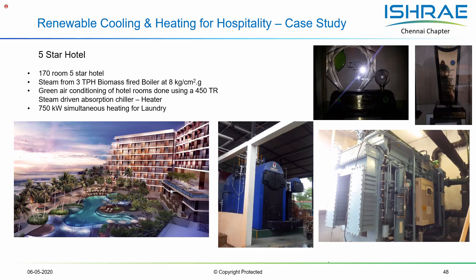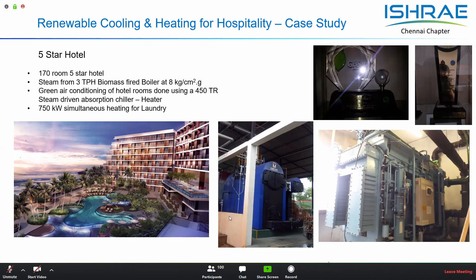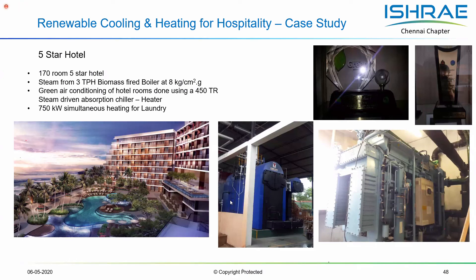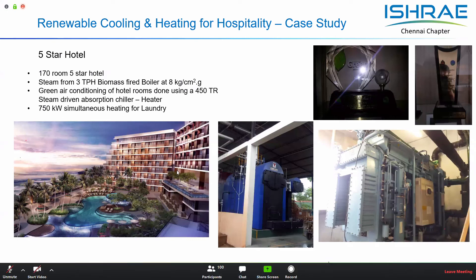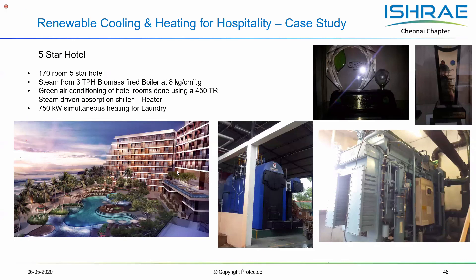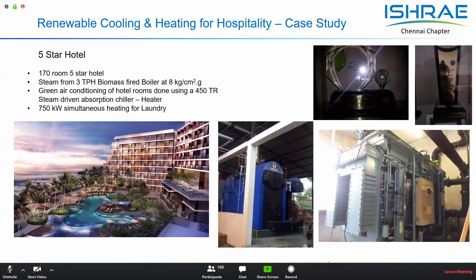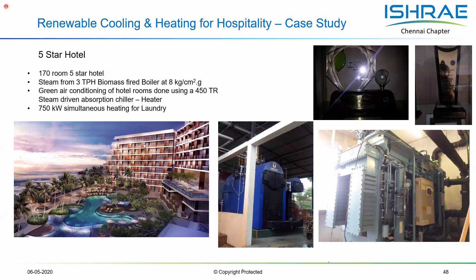One such illustration is a 170-room five-star resort hotel where this concept has been successfully implemented. A 450-ton chiller with a heating module is driven by a biomass boiler, making it greener, and caters to both cooling and heating demands simultaneously. Cooling is used for air conditioning and heating can be used for laundry, spa, and similar requirements. The same concept can be replicated in an industrial context or in hospitals or pharma industries where there is a high simultaneous demand for both cooling and heating.